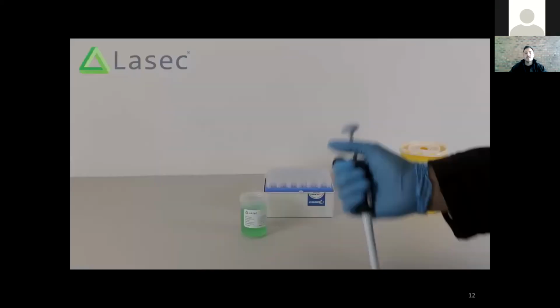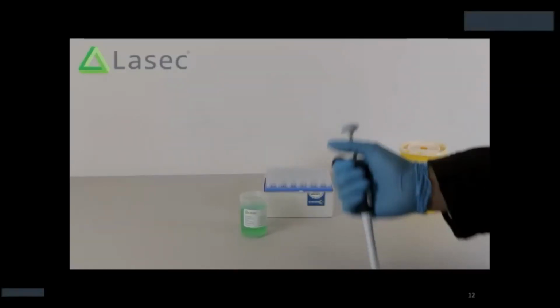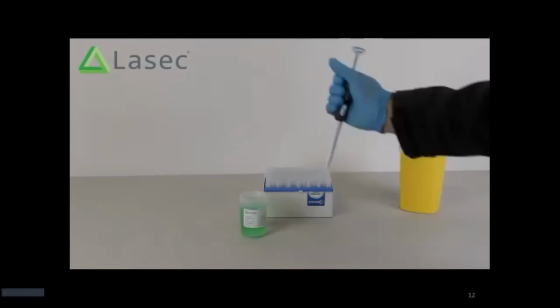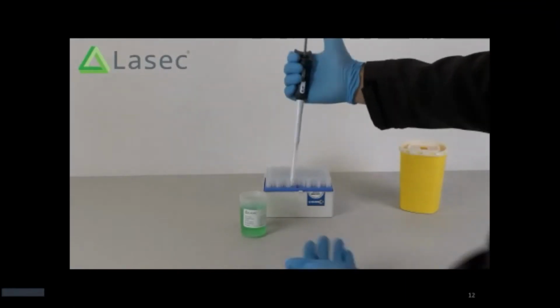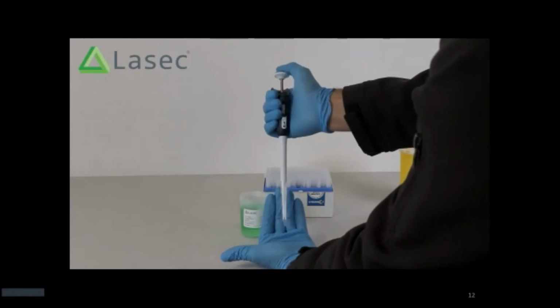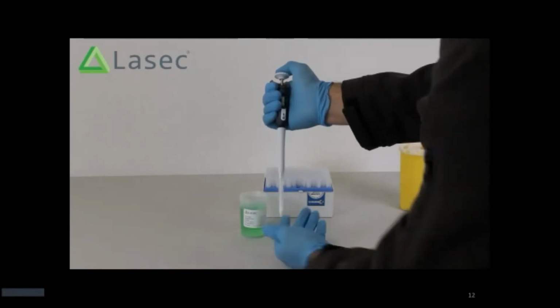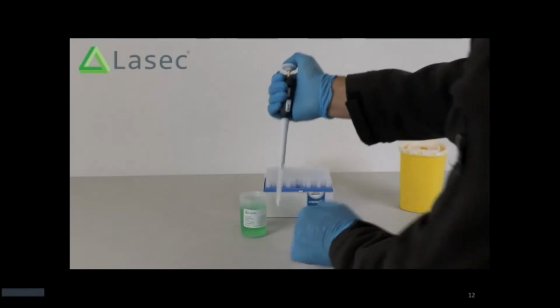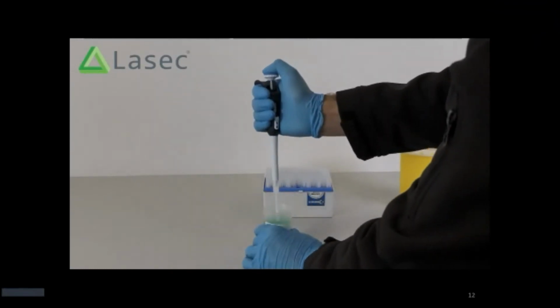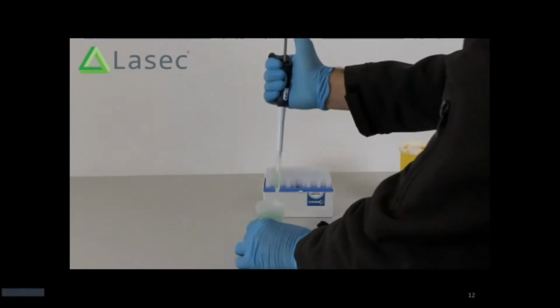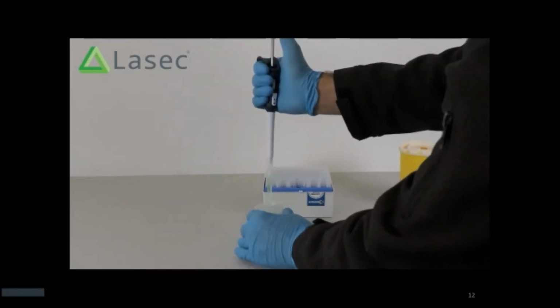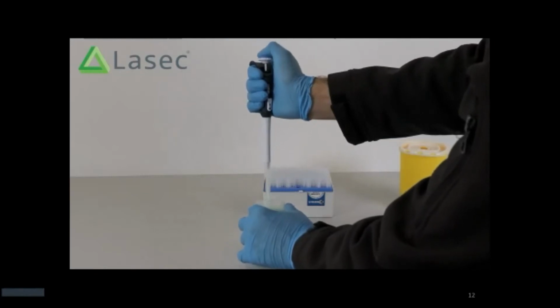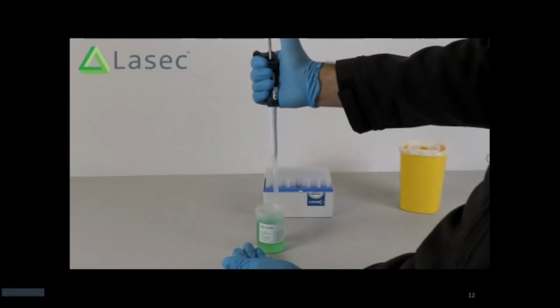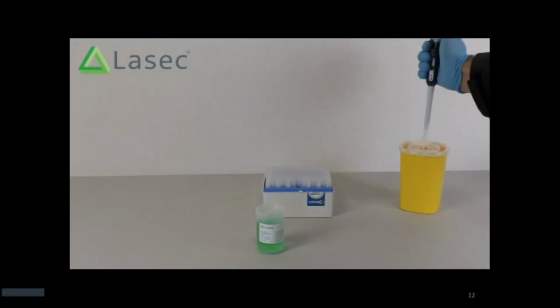All right, so now basically it's a physical piston. So now that we've removed that elastic properties of the air displacement pipettes, it means that we can now pipette accurately and precisely a number of different problem samples. So in this video, I'm just demonstrating how the piston looks inside the pipette. So essentially it's now been removed from inside and placed into the tip holder, into the tip itself. You will see how it draws up that liquid, much like a syringe. And to dispense it, you simply do the same principles as you would with an air displacement pipette.